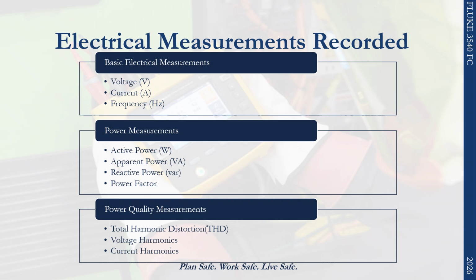The monitoring system records several types of electrical measurements. Basic electrical measurements include voltage, current, and frequency. The device also records power measurements such as active power, apparent power, reactive power, and power factor. In addition, the monitor tracks power quality measurements like total harmonic distortion, voltage harmonics, and current harmonics, which can indicate abnormal electrical conditions.